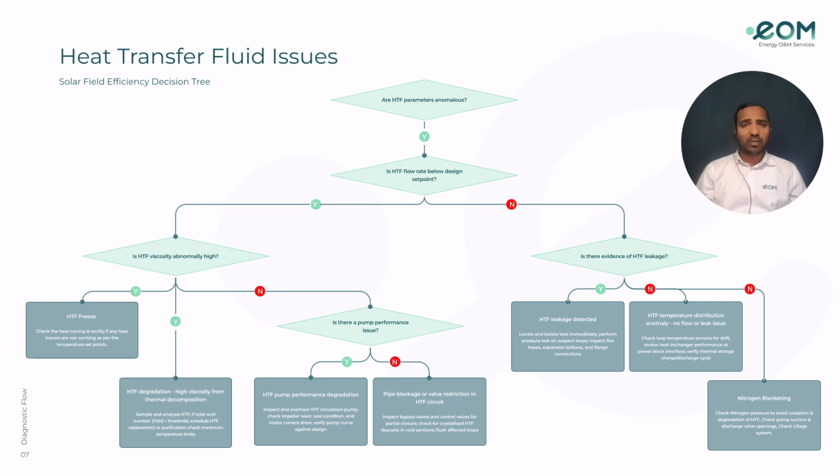Freeze-related problems are commonly associated with inadequate heat tracing performance, especially during low temperature conditions. Thermal degradation, on the other hand, is usually identified through HTF laboratory analysis and elevated total acid number values. When degradation becomes severe, purification or fluid replacement may be required. If viscosity is normal, the next focus becomes pump performance.